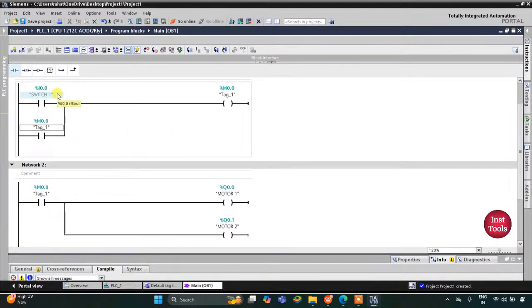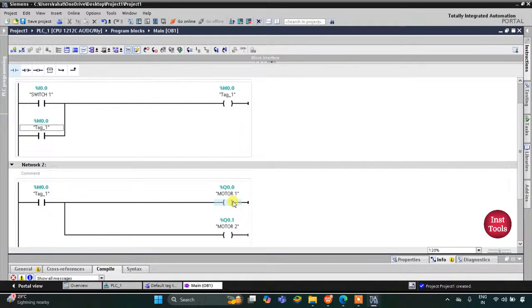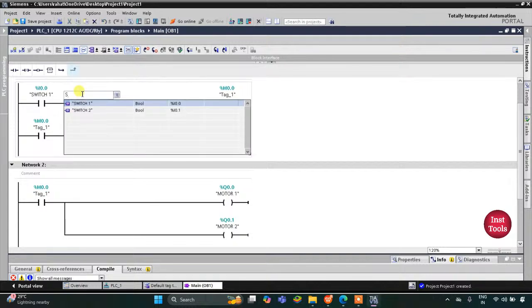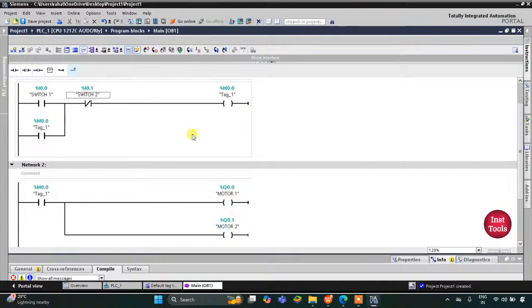Now when Switch 1 is pressed, M0.0 gets true, and when M0.0 gets true Motor 1 and Motor 2 turn on. When Switch 1 is turned off, due to latching M0.0 still remains true. When it remains true it will keep Motor 1 and Motor 2 on. To turn off these motors with Switch 2, we will use a normally closed contact here and it will be Switch 2. When M0.0 is true and Switch 2 is pressed or turned on, as it is a normally closed contact in true state it will not allow current to flow. As a result M0.0 gets off.